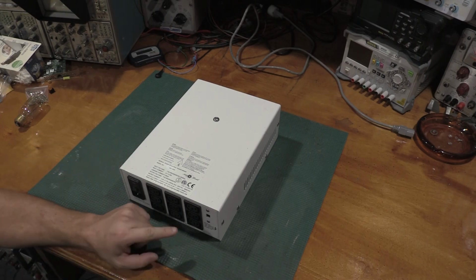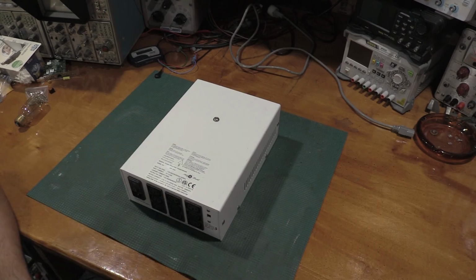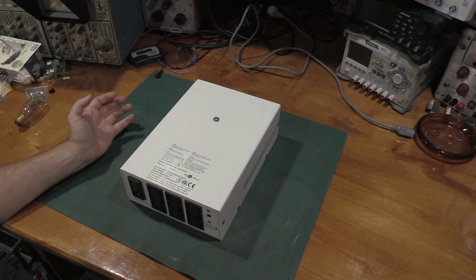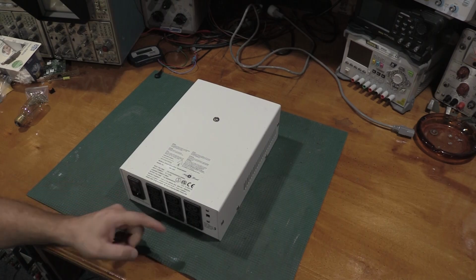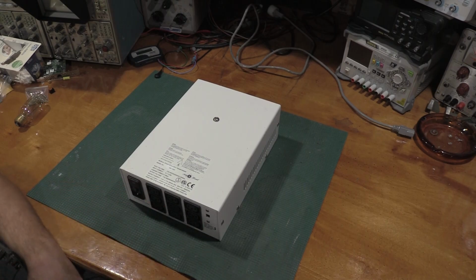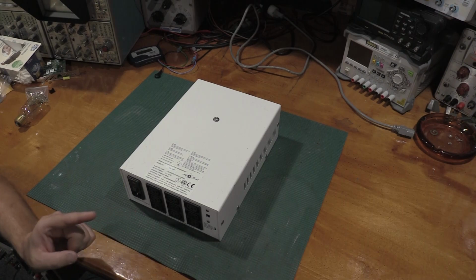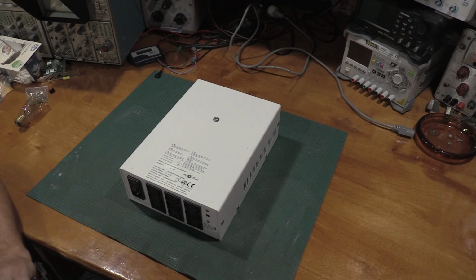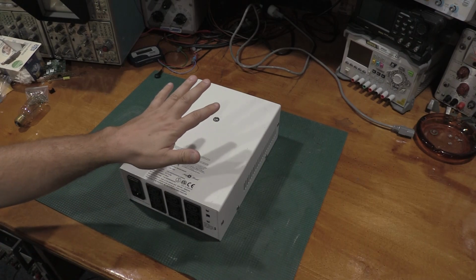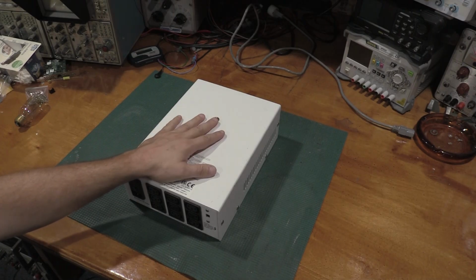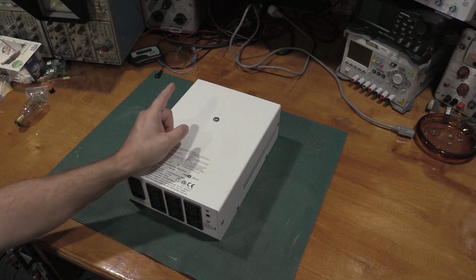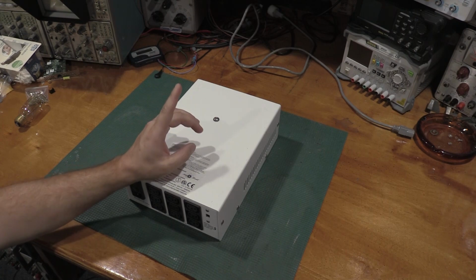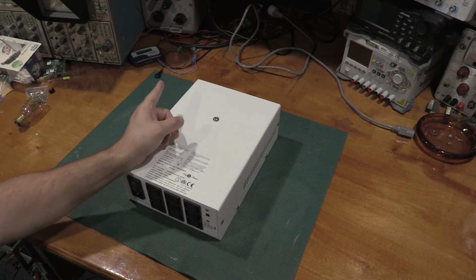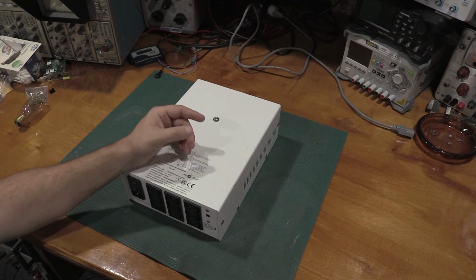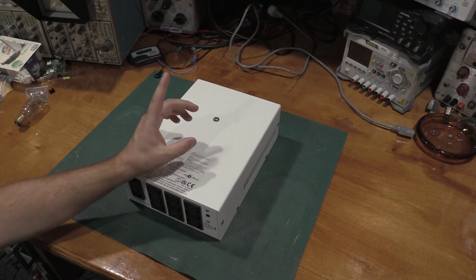I had another one. This is the 230 volt, which I haven't had to work on much 230 volt stuff recently. So this will actually take 120 in and step it to 230 volt phase to neutral. So where I am in North America, we have 240 volts, but we do not have 240 volts phase to neutral. We have 240 volts phase to phase. It's actually the same phase, it's just a center tap off the transformer on the pole.